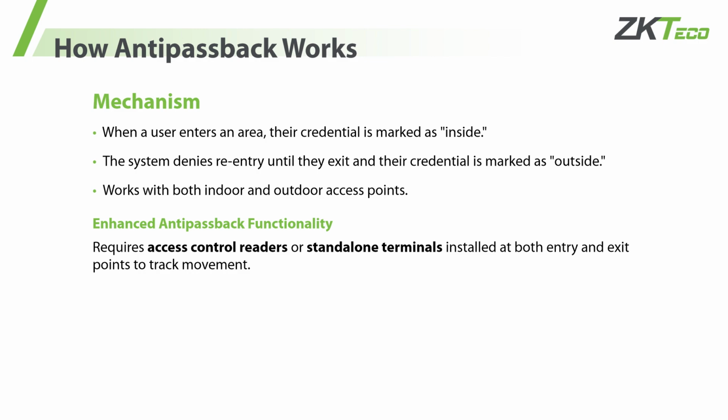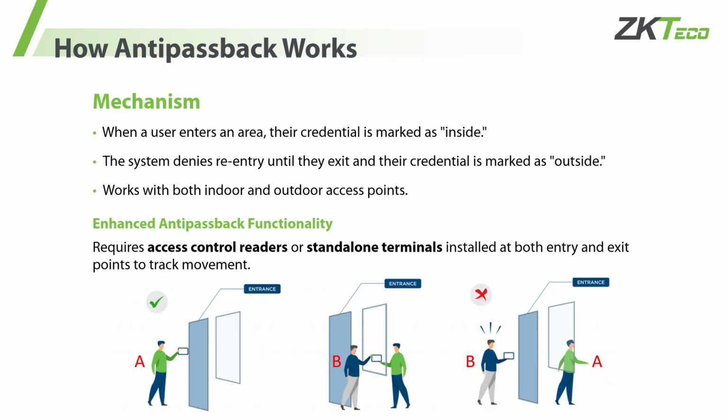Specifically, when a cardholder enters an area, if card readers are installed at both the entrances and exits of the area, the cardholder cannot use the same card to enter the area again at the same time. This avoids the situation where one person enters and hands the card to another person for use. For example, we can see in the figure that when person A lends the card to person B after successful verification, A can enter the room without the card, and B cannot enter the room with the card.